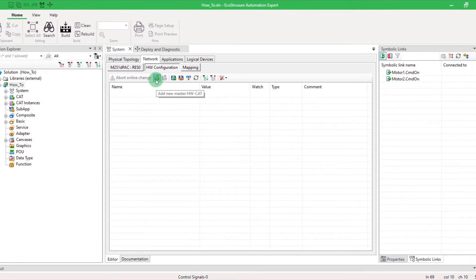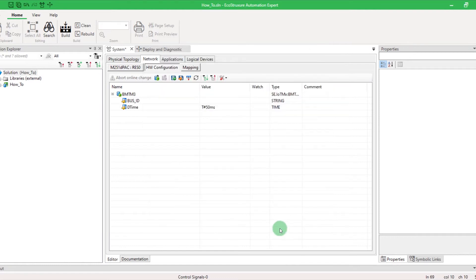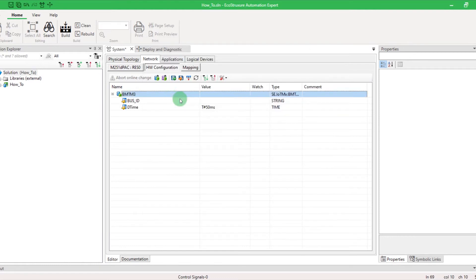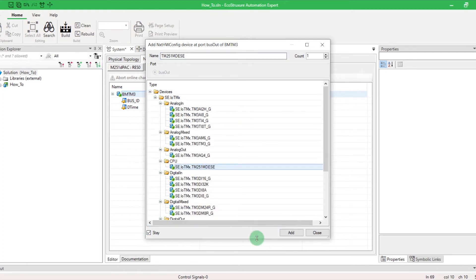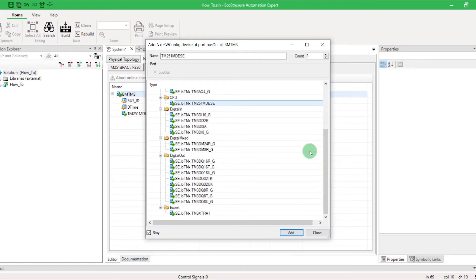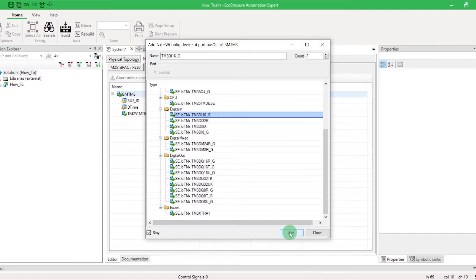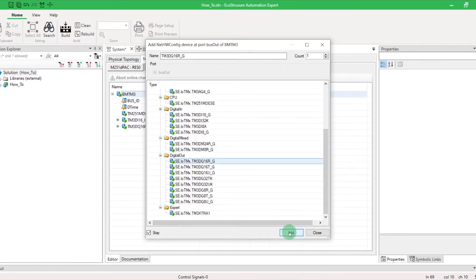By clicking on the Add New Master button, you can add the bus TM3. Right-click on the bus and select Add to choose the I.O. modules. Click on the Stay box to keep the pop-up opened. Be careful — make sure that you first add the CPU M251 and then add the I.O. modules in the same order that they are physically connected.